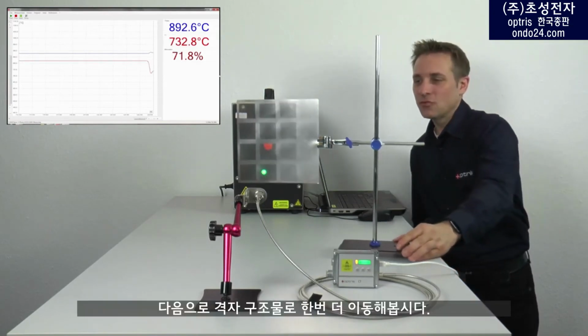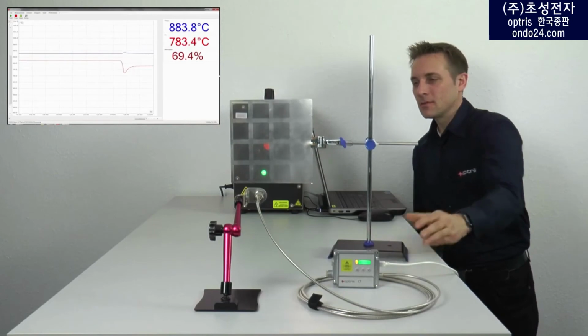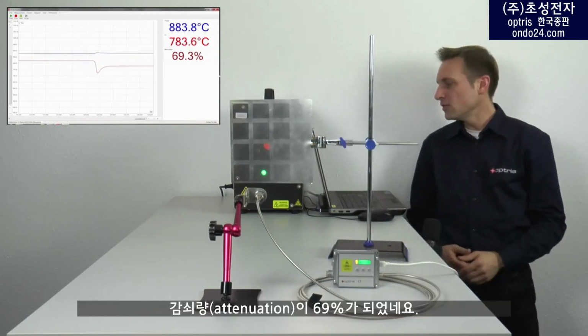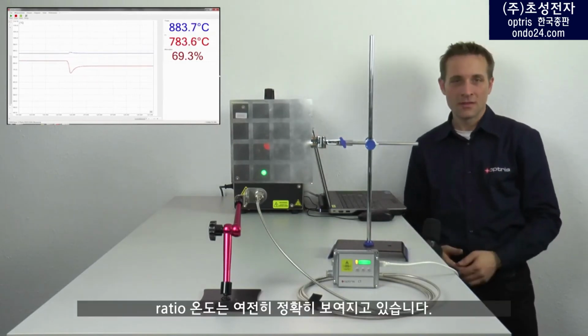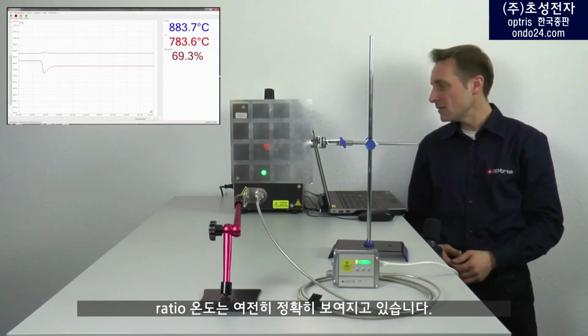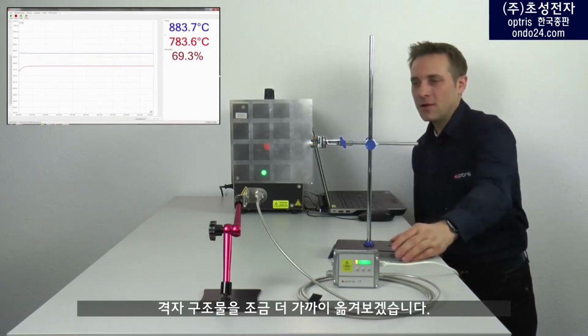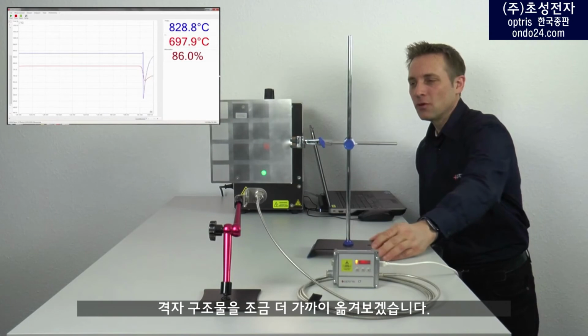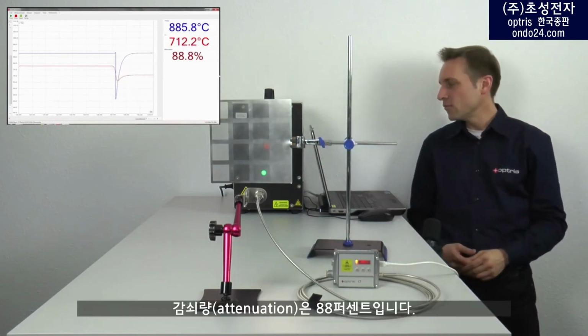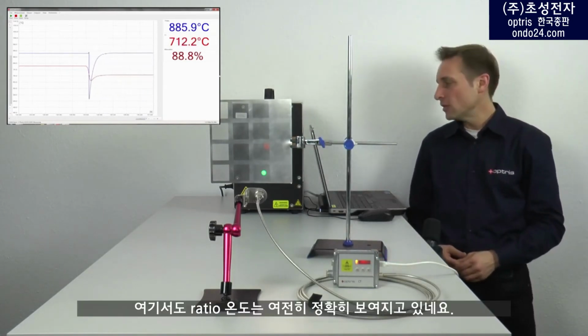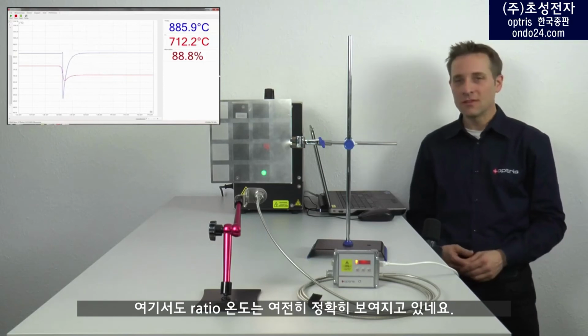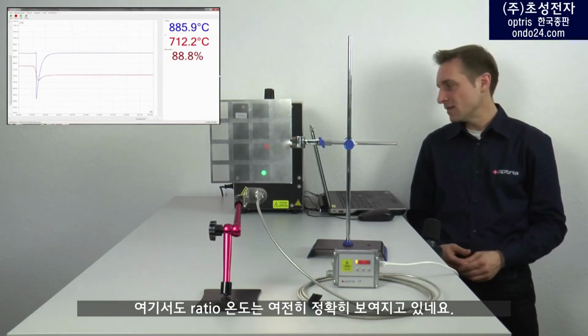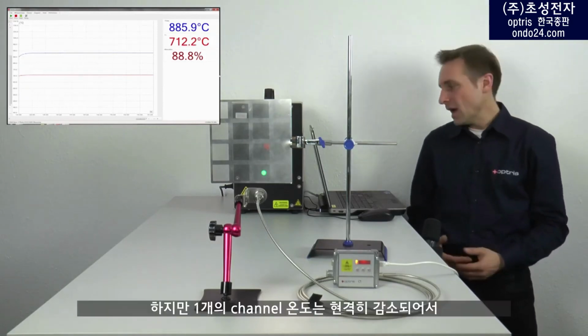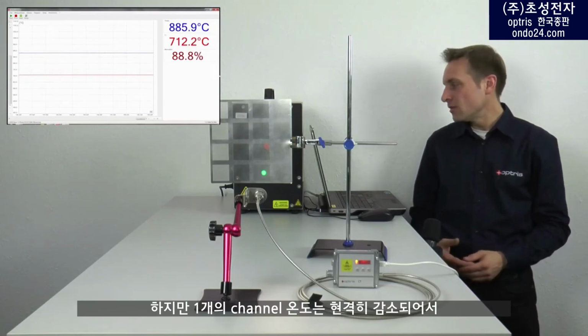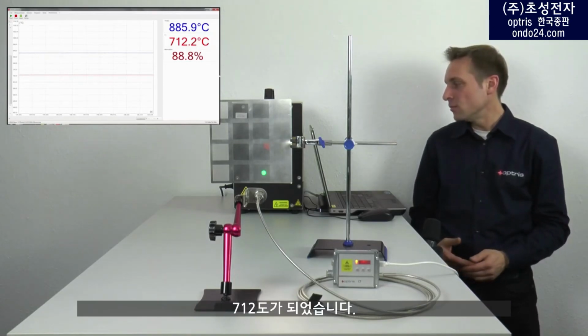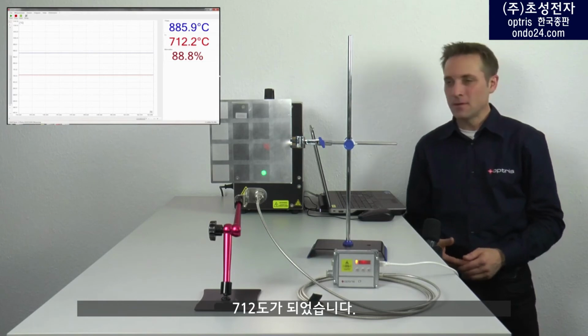Let's look at the next grid structure. Here we have an attenuation of 69%, and the ratio temperature is still displayed correctly. Let's choose a closer grid structure. We have an attenuation of 88%, and here too our ratio temperature is still displayed correctly. The one-channel temperature, as we can see here, has clearly reduced down to 712 degrees.